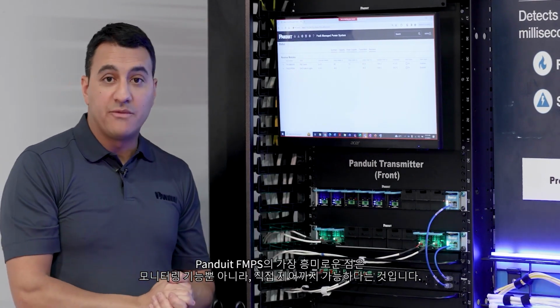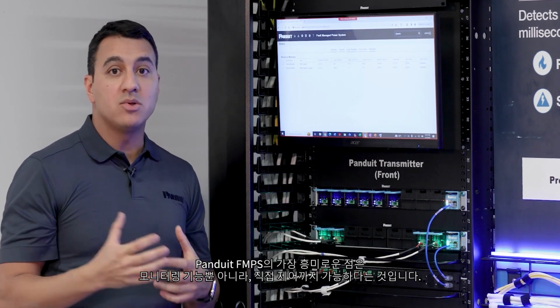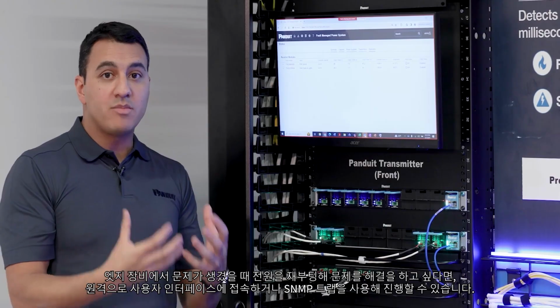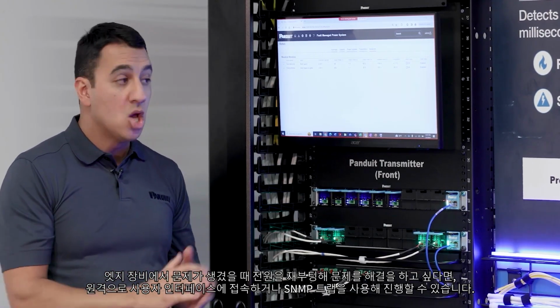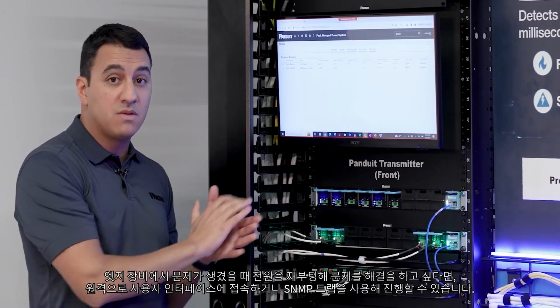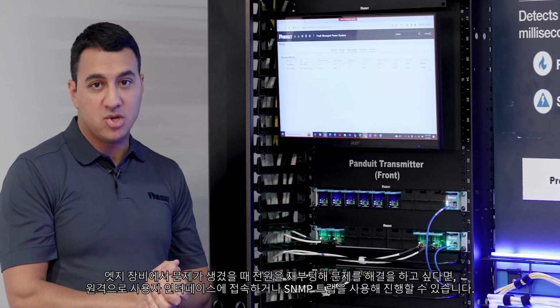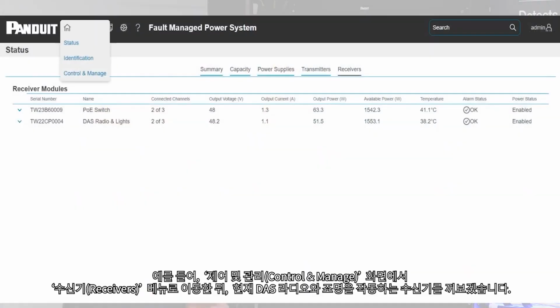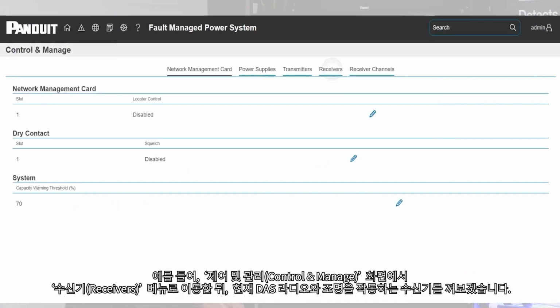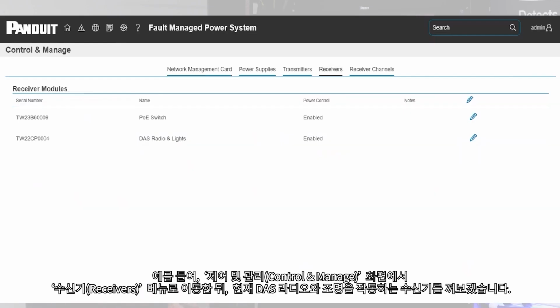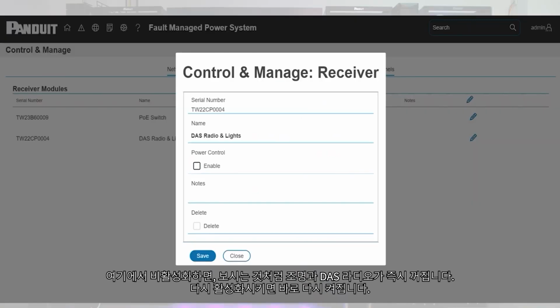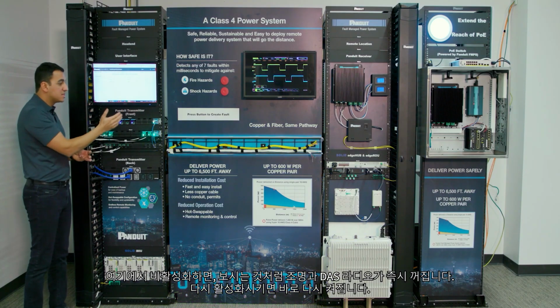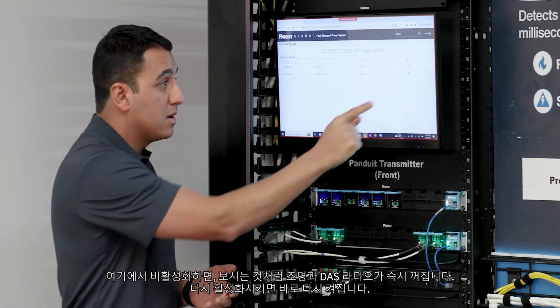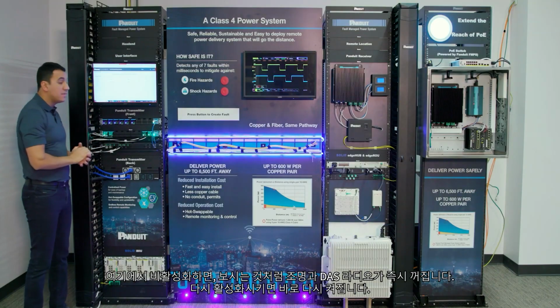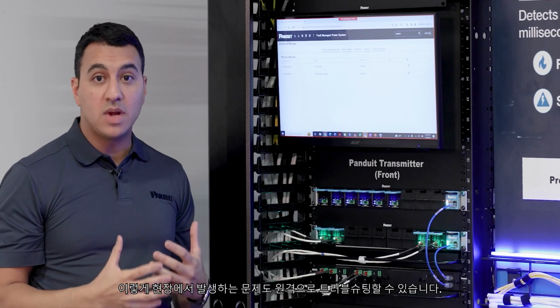A very interesting feature of the Panduit fault managed power system is not just the monitoring, but also the ability to control. So if you want to troubleshoot a device at the edge by simply power cycling it, you can do that remotely, whether by logging into the user interface or by using SNMP traps. So for example, I'm going to go to the control and manage screen here and go to our receivers, and I'm going to turn off our receiver that's powering the DAS radios and lights for us. So I simply go here, disable it, and you can see the lights and the DAS radio go off instantly. I can come back and turn that on, and there you go. This can be done remotely to troubleshoot any issues in the field.